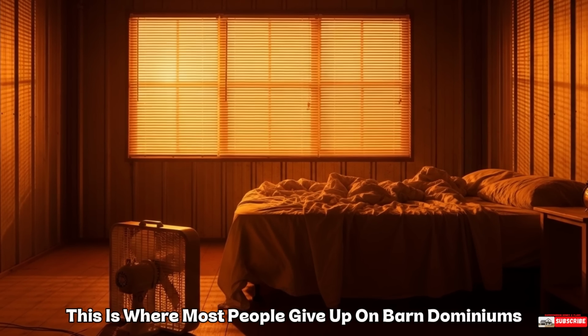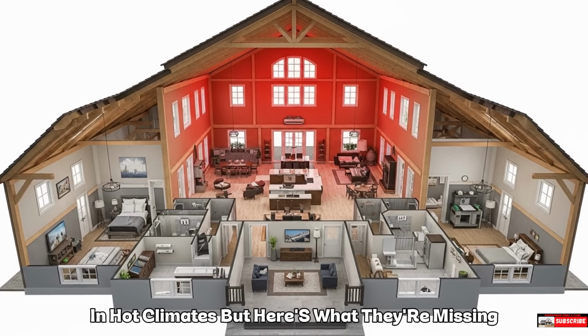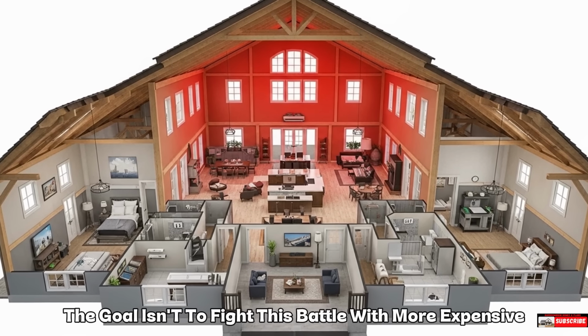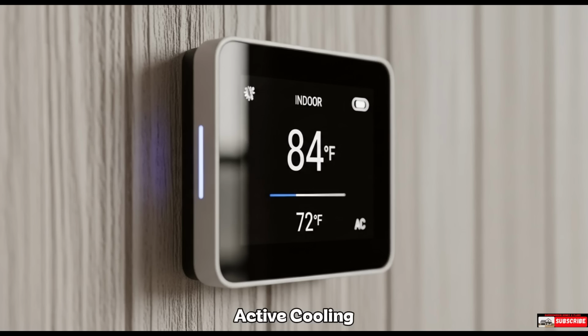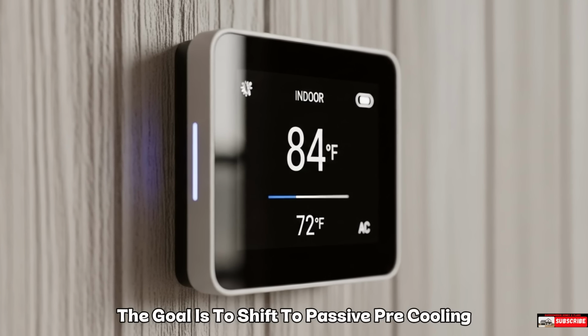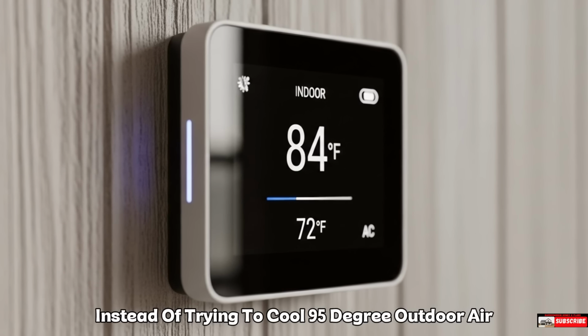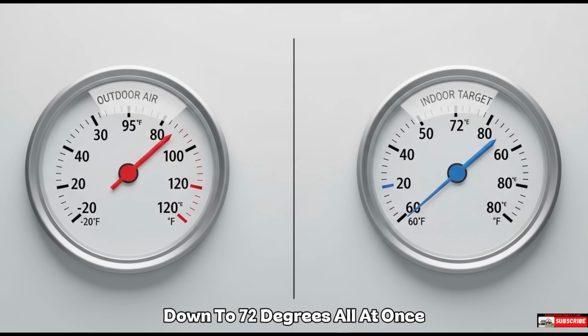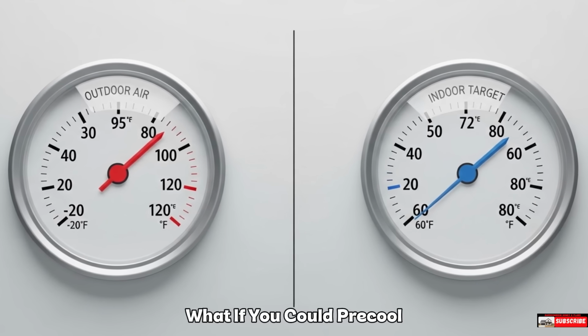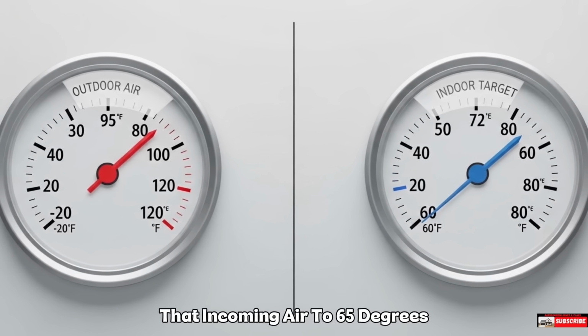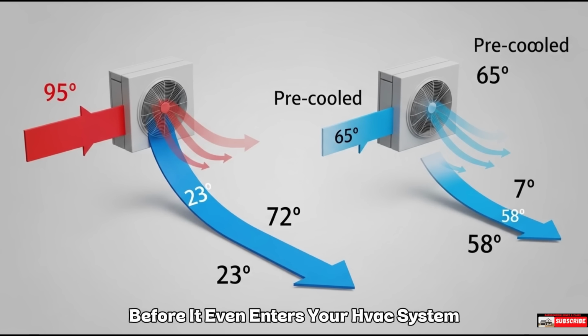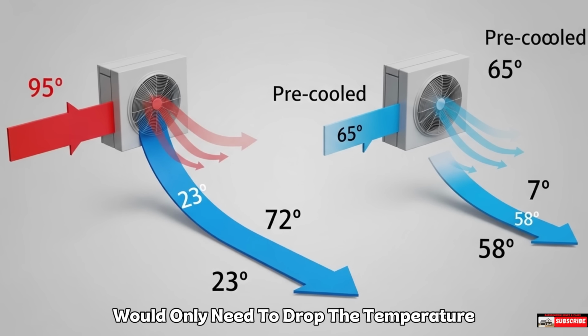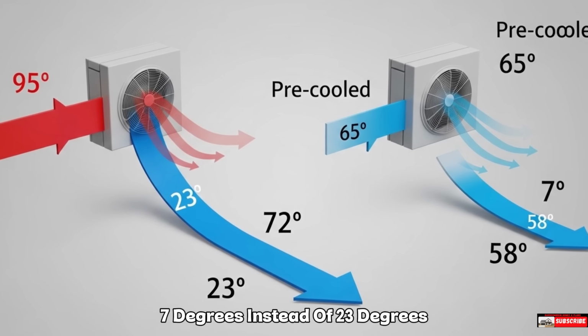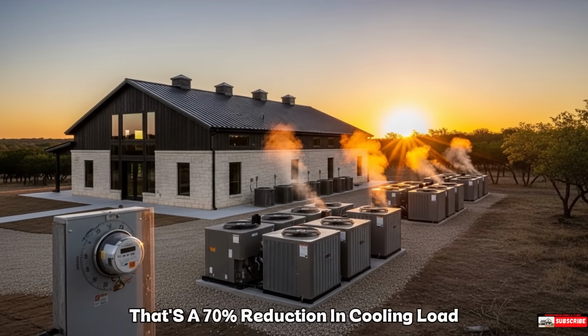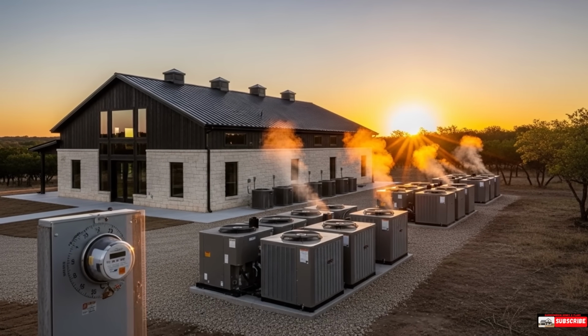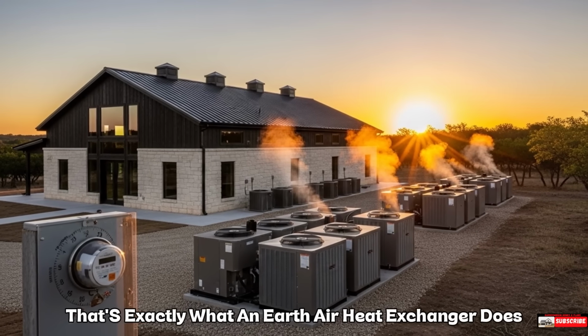This is where most people give up on Barndominiums in hot climates. But here's what they're missing. The goal isn't to fight this battle with more expensive active cooling. The goal is to shift to passive pre-cooling. Instead of trying to cool 95-degree outdoor air down to 72 degrees all at once, what if you could pre-cool that incoming air to 65 degrees before it even enters your HVAC system? Your air conditioner would only need to drop the temperature 7 degrees instead of 23 degrees. That's a 70% reduction in cooling load. That's exactly what an earth-air heat exchanger does.